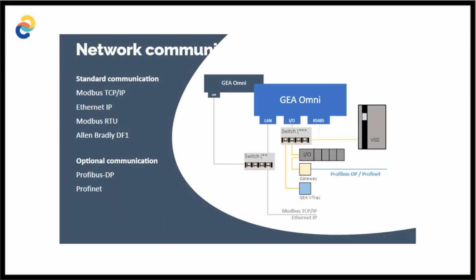And network communication. As I mentioned, communication in this modern day and age is so easy, but also we recognize that customers also have their own protocols sometimes. So we built into the GEA Omni some standard communication features. So if you're using Modbus or Ethernet or Modbus RTU, or you have an Allen Bradley PLC, which is controlling your plant, Omni can communicate with it. And we have other options as well, like Profibus or Profinet. So we try and cover the spectrum of communication modules that are current in the world today.